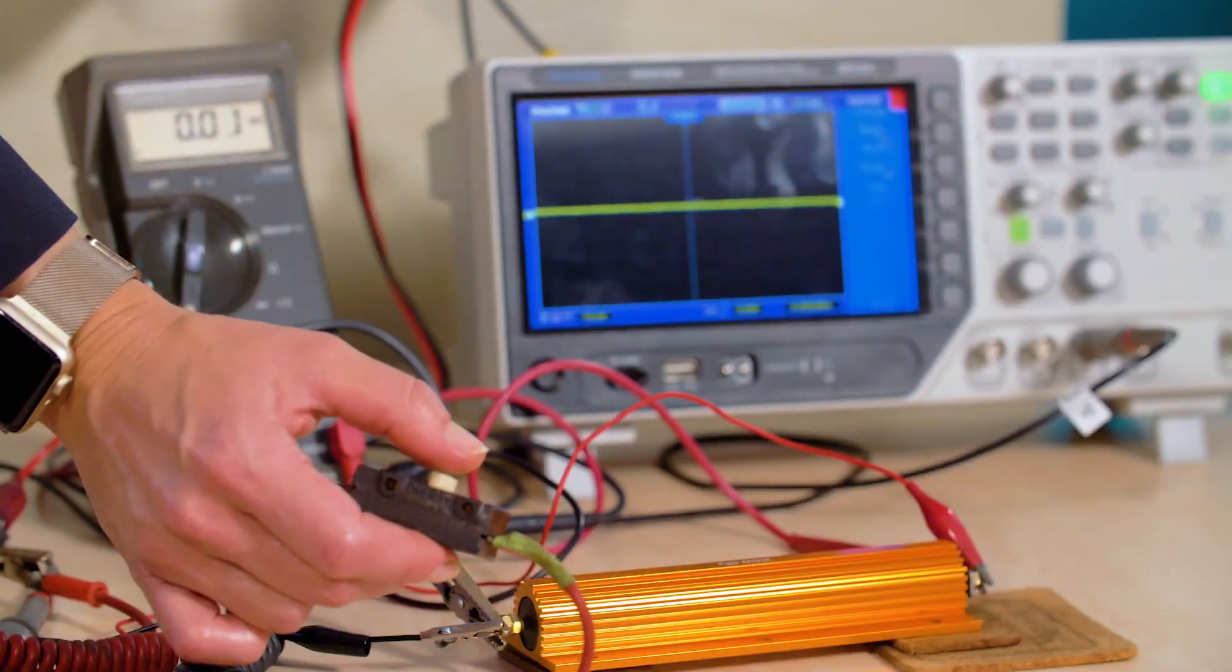We can simulate the 150 percent peak power operation. Now 150 percent peak power for these particular supplies means they can put out 7.5 amps at 24 volts and do it for four seconds. Something that puts out 7.5 amps for a few seconds is a relatively big inductive load bigger than anything we've got available for our demo.